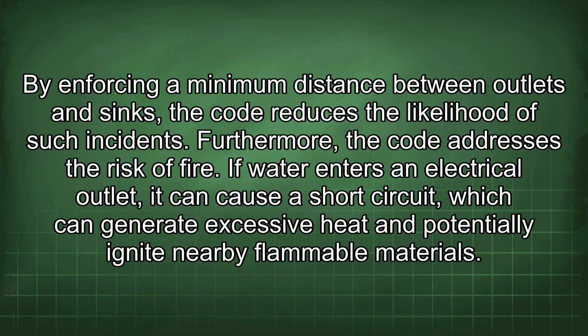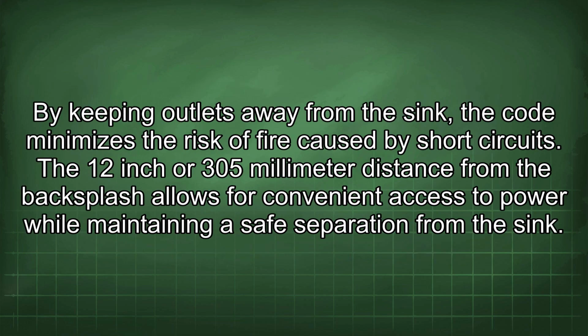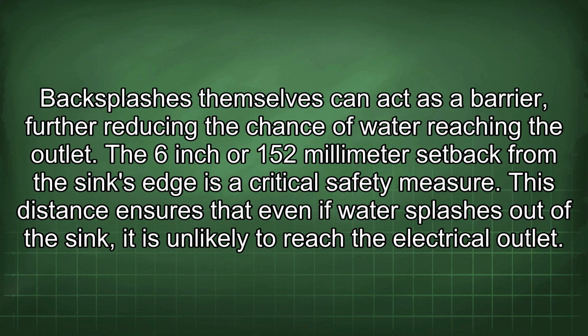Furthermore, the code addresses the risk of fire. If water enters an electrical outlet, it can cause a short circuit which can generate excessive heat and potentially ignite nearby flammable materials. By keeping outlets away from the sink, the code minimizes the risk of fire caused by short circuits. The 12-inch or 305 mm distance from the backsplash allows for convenient access to power while maintaining a safe separation from the sink. Backsplashes themselves can act as a barrier, further reducing the chance of water reaching the outlet.